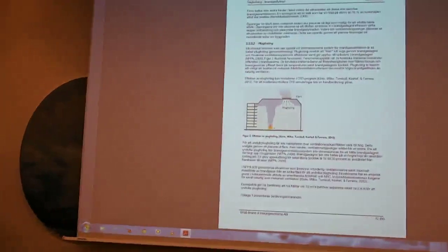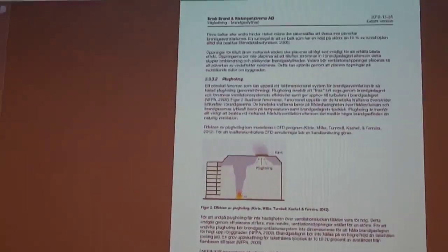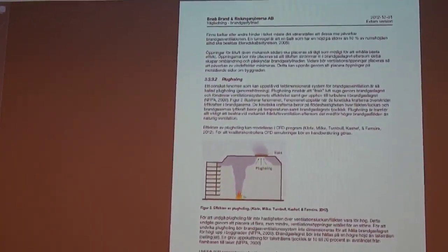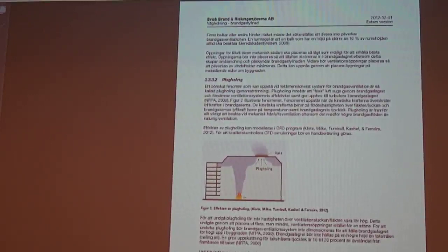And so we work with the aspects of it. And the different kind of ventilation systems to work with, if it's thermal or if it's mechanical, what's the difference and how to see the problem with the different systems. Also some specific things that could happen when you work with different kind of systems, like plug holing. I don't know if you know about it, but it's when you're using mechanical fans to evacuate smoke, it could be a phenomenon, some problem that you only evacuate the fresh air, not the fire gases.